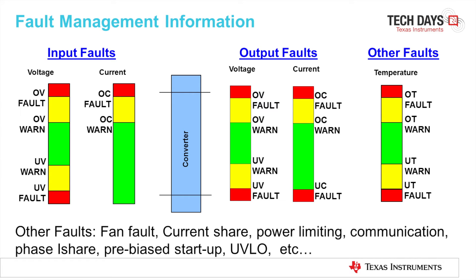There is also extensive fault management information, such as input faults — both voltage and current — output faults in voltage and current, as well as other faults such as temperature. For each parameter there is an over and under warning as well as fault. For example, for voltage, there is an over voltage fault and over voltage warning — any voltage exceeding a maximum over voltage setting of two volts will cause an over voltage fault — and there are also under voltage warnings and faults. There is other fault monitoring as well, such as fan fault, current share fault, power limiting, communication. For multi-phase converters, also a current share per phase fault, pre-biased startup fault, and UVLO.